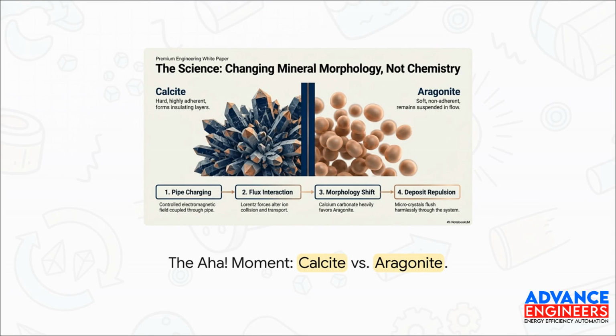Normally, calcium carbonate forms as calcite. Those are sharp, hard, highly adhering crystals. That's what builds up that nasty insulating layer. But after passing through the AE flux field, the mineral is forced to precipitate as aragonite, which consists of smooth, soft, suspended microcrystals. And the crazy part?